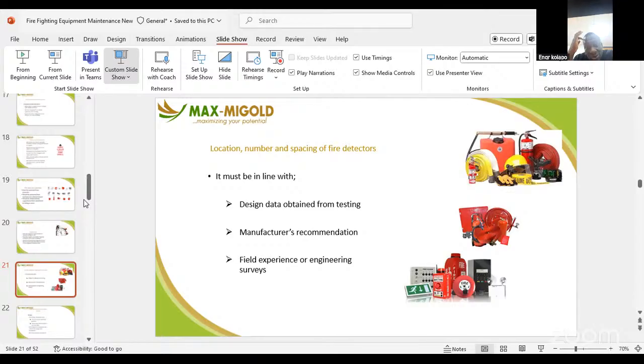So you don't need to bother yourself about how to locate, space or number fire detectors. You know why? The NFPA 72, which speaks to the detection system, has given a guideline on what we need to do. So when we have the layout of your facility, following NFPA 72, including consideration for pillars and beams, we can at least estimate how many smoke detectors you should have in the building. If there is also a corridor, like a banking hall, school premises, or hotel, that kind of setup is different from an office area, a factory, or a warehouse, because of the design and, of course, the storage condition and how people use the facility.